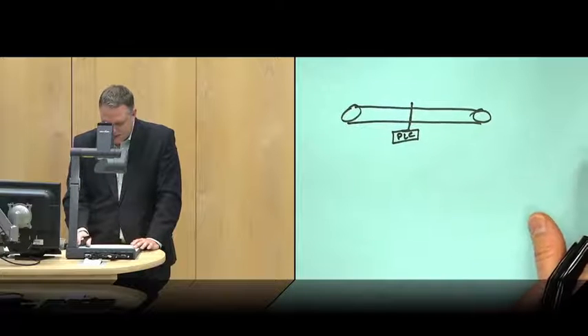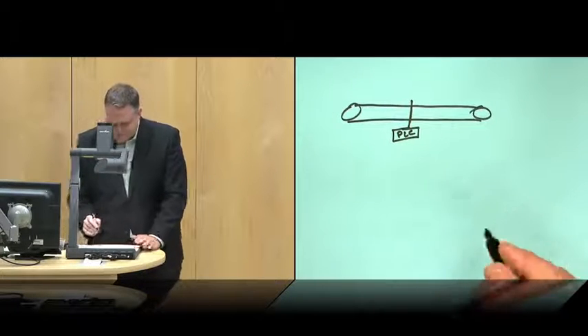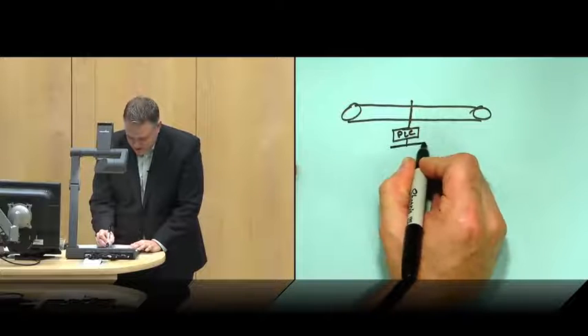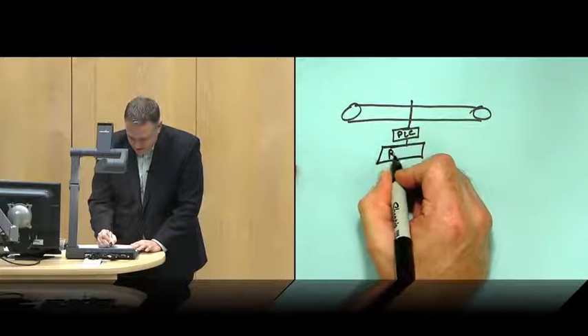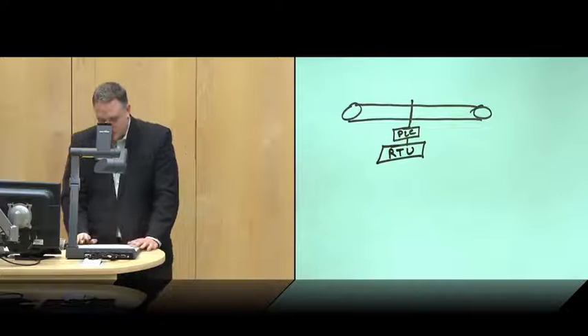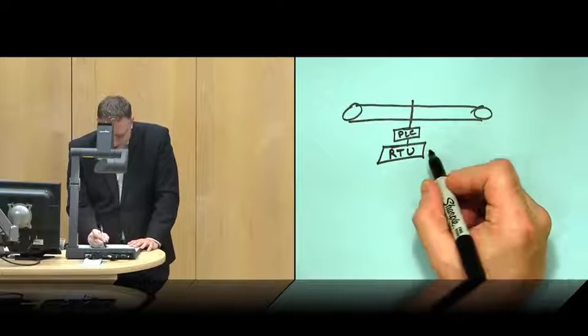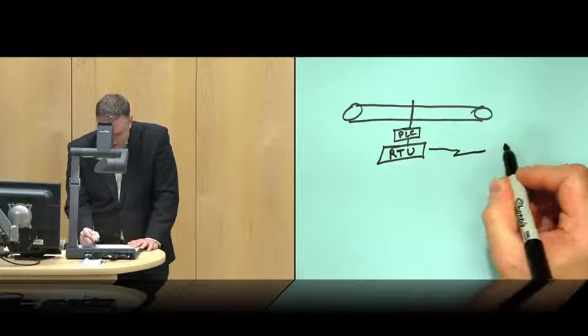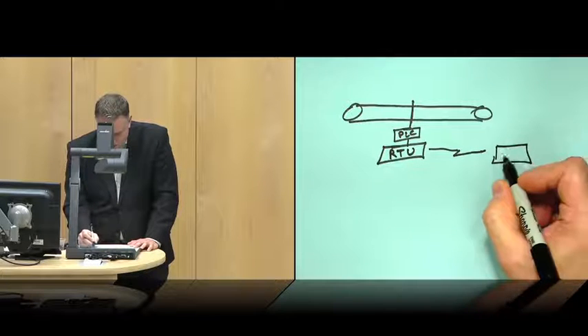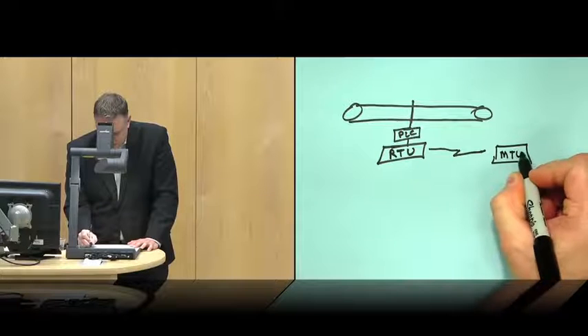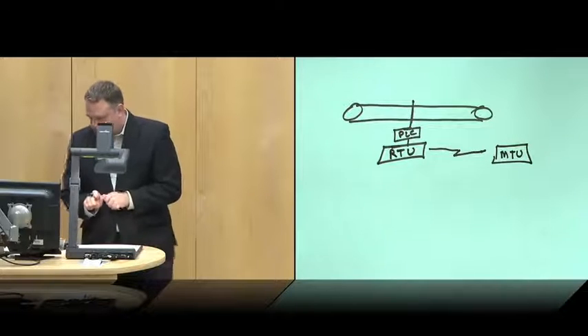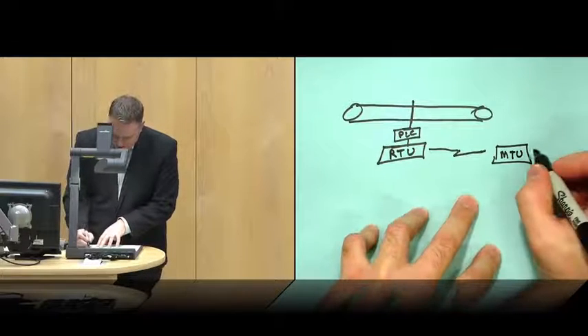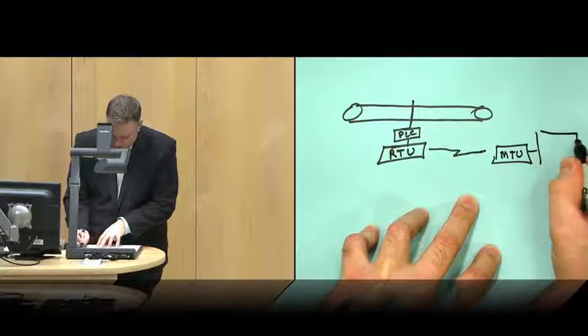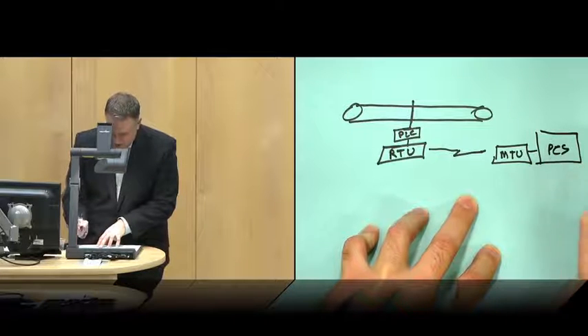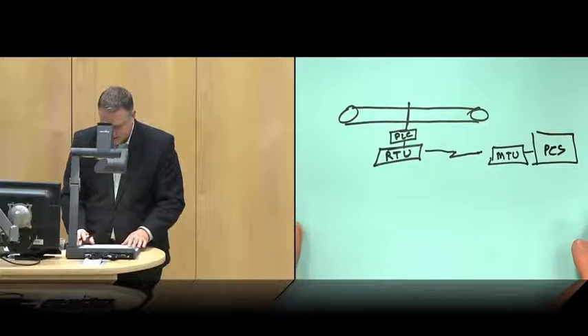Now, the PLC isn't going to be able to communicate with anything on its own. So what it's going to do is have a connection to some type of remote terminal unit, or RTU, and that is going to communicate with some type of master terminal unit. The master terminal unit is probably going to be connected to some type of process control system.